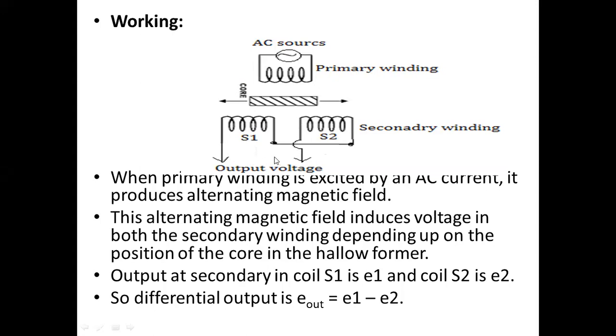So there is no output at all. If any displacement occurs, it is not at the center, not the null position. If it is left of the null position, EMF induced E1 is greater than E2. If the soft iron piece is right of the null position, E2 is greater than E1. So for the left side it gives a positive value, and for the right side a negative value. That's how displacement is measured.